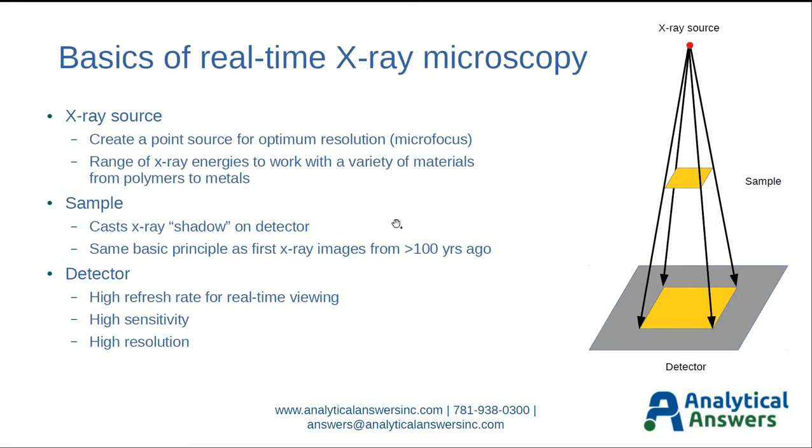The basics of a real-time X-ray microscope really haven't changed much in a long time. Technology has led to incremental improvements. You start with an X-ray source, and what you're trying to do is create a point source, a micro-focus spot, so you have the highest resolution in your image possible. By having the X-rays come from a single point, then you have sharp edges in your images.